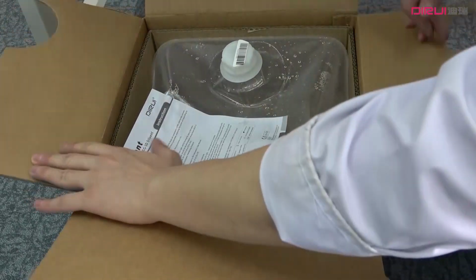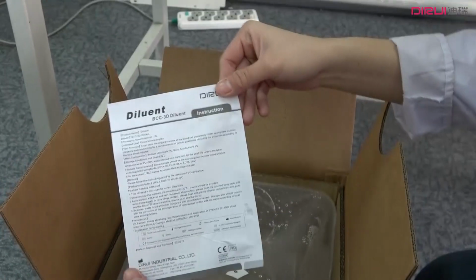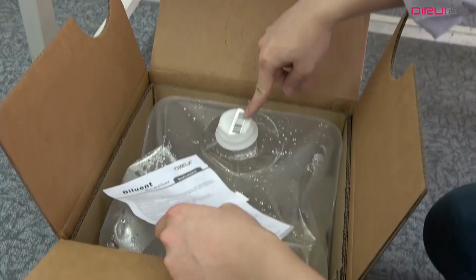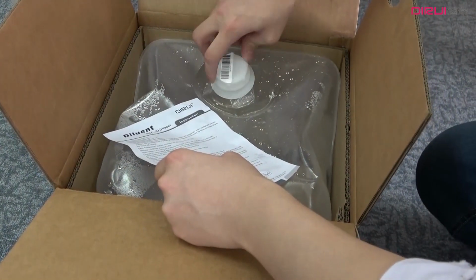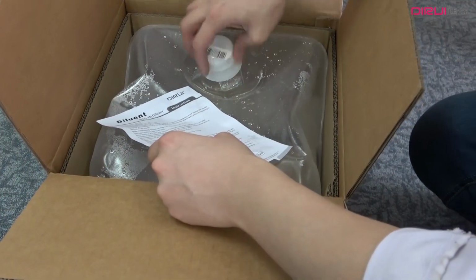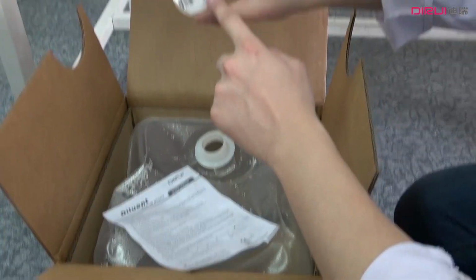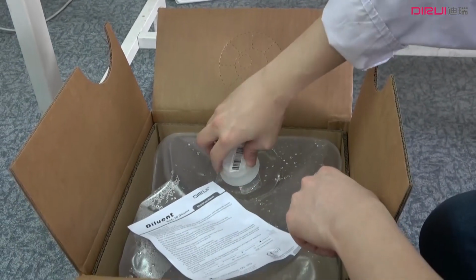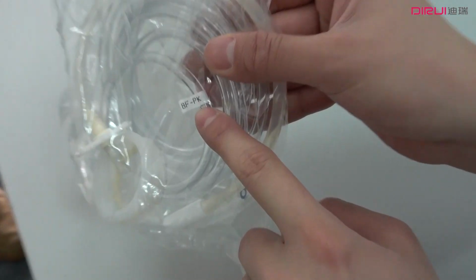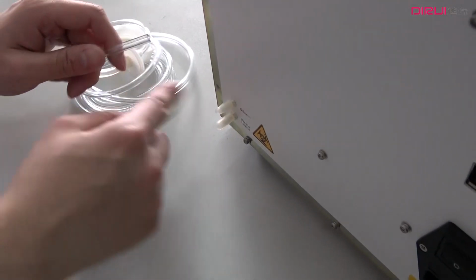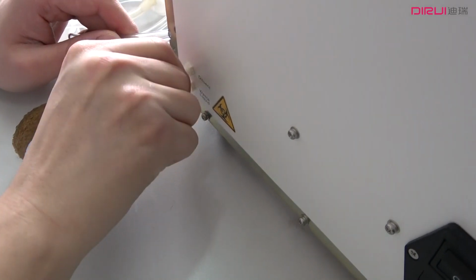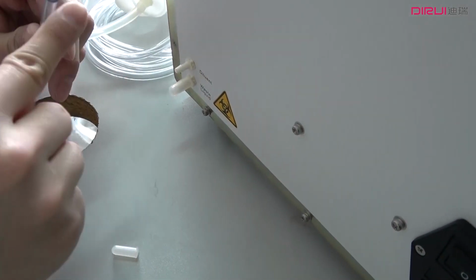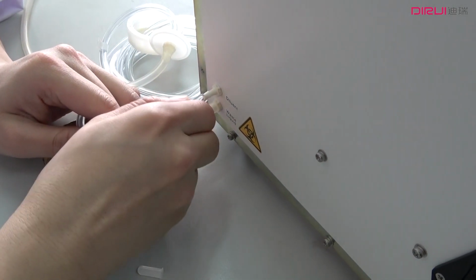From the bottle cap you can see a barcode. This code is used for registration. Take out the diluent tube, remove the protector and connect one side of the tube with the instrument and insert the other side in the diluent bottle.